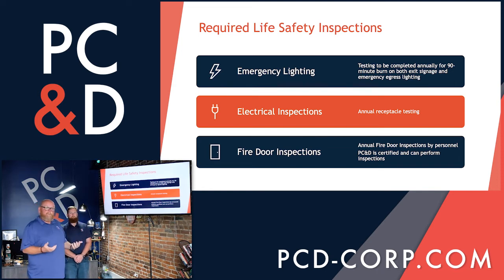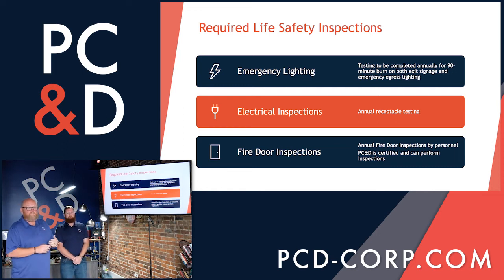So per government mandates and per CMS mandates, you have a certain amount of items, such as the sprinklers, the fire alarms, the items listed here, and the other things we'll be going through in the inspection today. You have to do those at a minimum. You also have to do those on a certain set time schedule, which is set by the federal government and the laws. You can be more stringent and do more than they ask, but they will set baseline minimums. So as Travis goes through these, and you see things like annual receptacle testing, annual fire doors, you do have things that are quarterly, you have things that are semi-annual. I don't know if you caught it or not, but on the sprinkler heads, you have some heads that are due 5 years, 10 years, 20, even some 50.